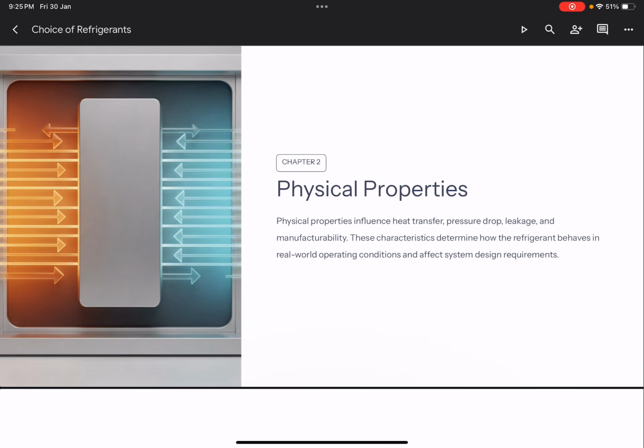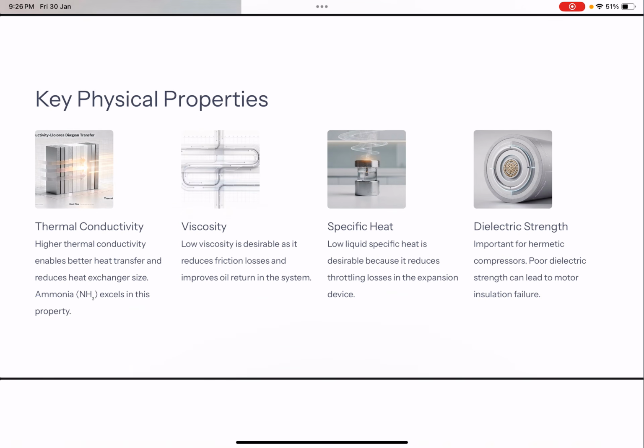The other set of properties, along with the thermodynamic properties, which are equally important in the choice of refrigerants are called physical properties. The physical properties of the refrigerants would influence a number of parameters, like heat transfer, the pressure drop, the leakage, as well as the manufacturability. These physical properties would determine how the refrigerant is going to behave in real-world operating conditions. So the key physical properties include the thermal conductivity, the viscosity, the specific heat, and the dielectric strength. What is generally desirable is a higher thermal conductivity, because a higher thermal conductivity would ensure better heat transfer and the heat exchanger size would be reduced. For example, ammonia has an excellent thermal conductivity.